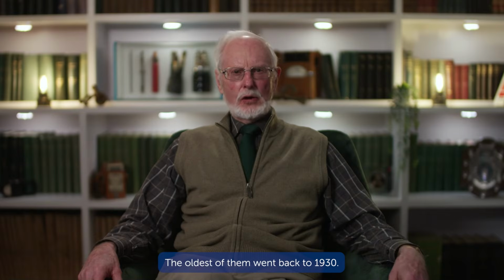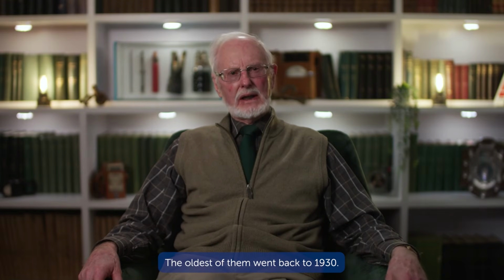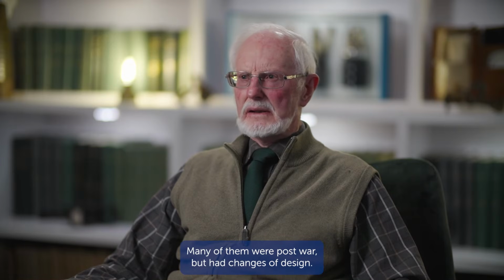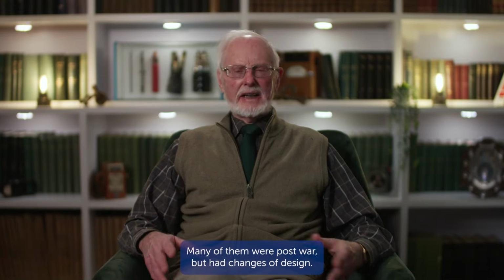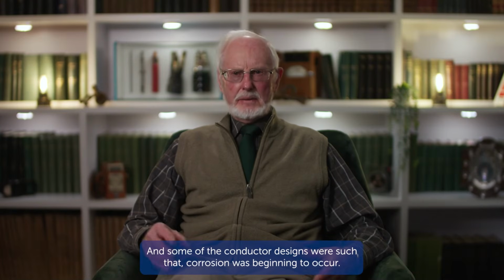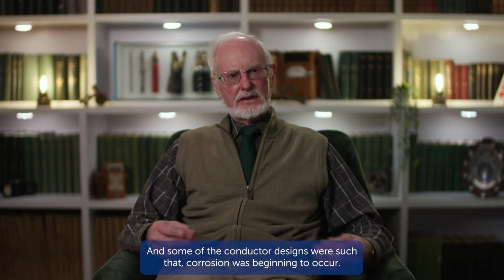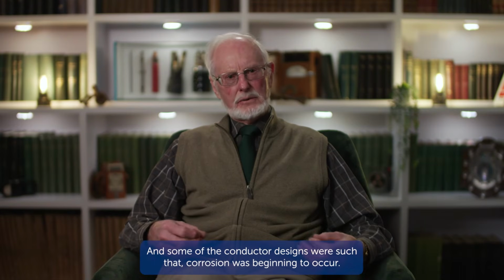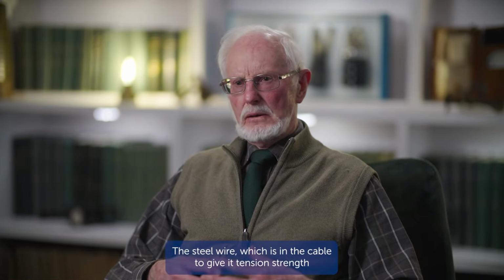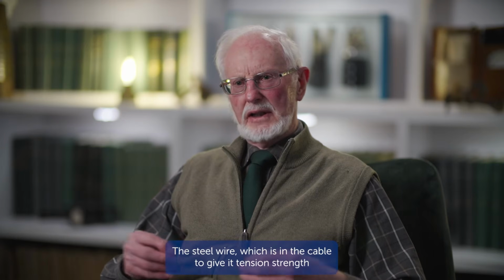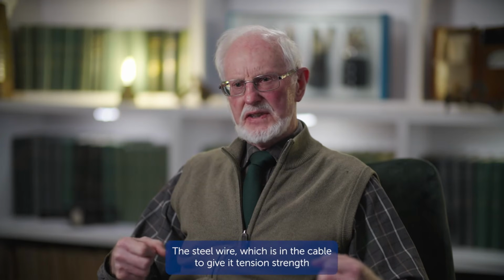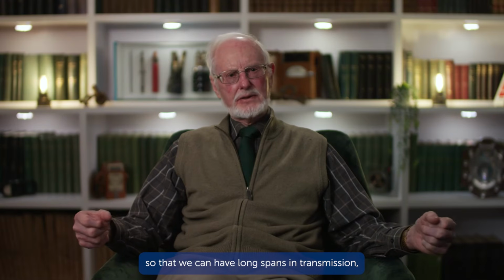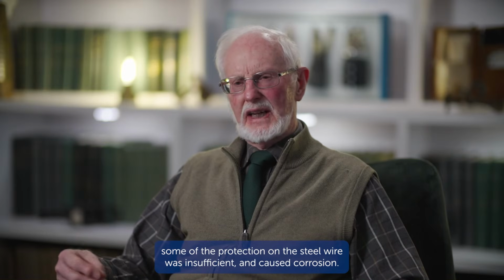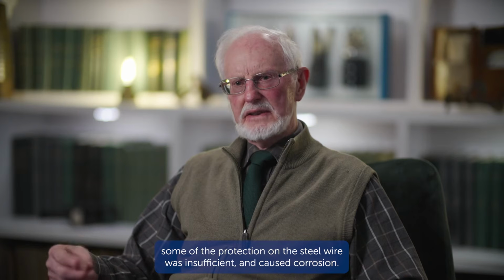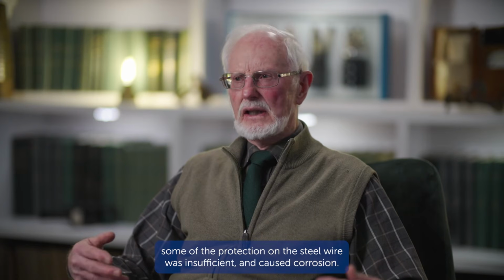The biggest challenge of my time in transmission was the ageing of the equipment, particularly the exposed transmission lines. The oldest of them went back to the 1930s. Many were post-war but had design changes, and some of the conductor designs were such that corrosion began to occur - the steel wire in the cable, which gives it tension strength for long spans in transmission, had insufficient protection in places, which caused corrosion.